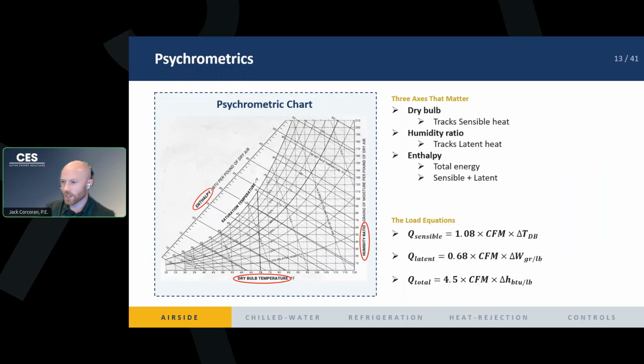The equations at the bottom here are pretty helpful for when you're sizing your coil or you're trying to figure out how big of a capacity you need for your unit. There's a sensible heat equation, there's a latent heat equation, and then your total enthalpy. Right, and that's just the diagonal line on the left side of the chart. So it's just a combination of the vertical and your horizontal axis. But basically, these equations are, the sensible one. As we can see, the last term is your dry bulb temperature, right? And that's what dominates that sensible heat. Your latent heat is the last term, right? That's your humidity ratio. That W is in grains per pound.